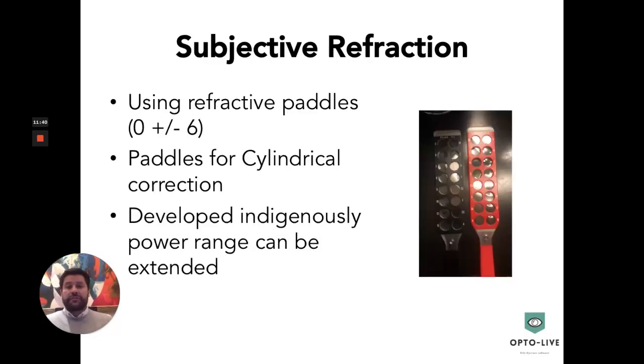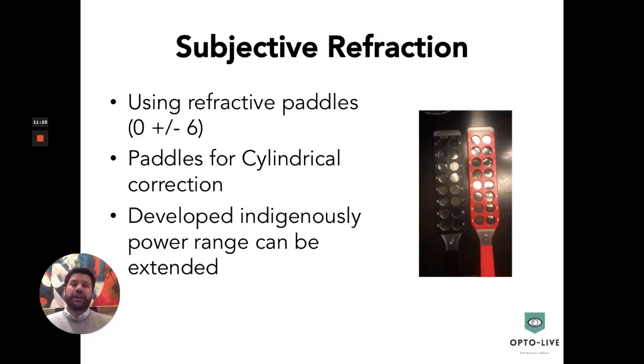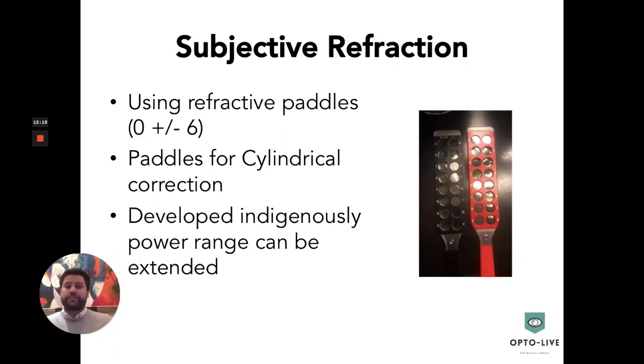Now that we have our objective prescription, what do we do for subjective refraction? Using the same charts shown earlier, we have developed refractive paddles — a red and a black paddle, one being a plus paddle and one a minus paddle — which contain different spherical and cylindrical prescriptions. These allow us to ascertain the new prescription required by the patient. This is developed indigenously by us; the power range can be extended as required and many different paddles can be created. Currently we have them from plus or minus up to six diopters.